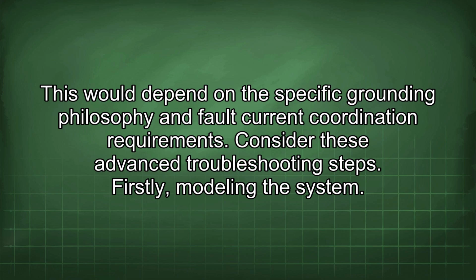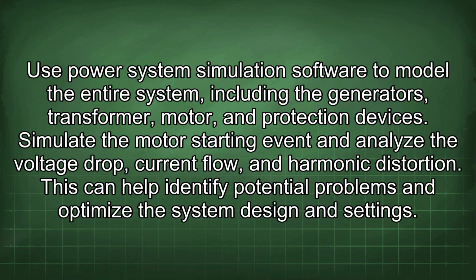Consider these advanced troubleshooting steps. Firstly, modeling the system. Use power system simulation software to model the entire system, including the generators, transformer, motor, and protection devices. Simulate the motor starting event and analyze the voltage drop, current flow, and harmonic distortion. This can help identify potential problems and optimize the system design and settings.